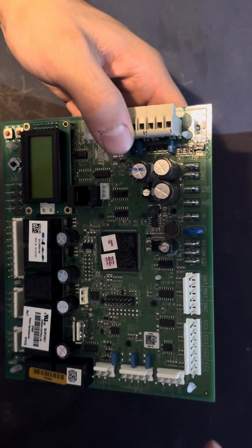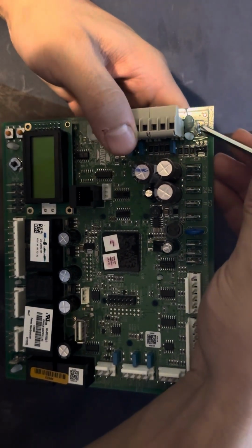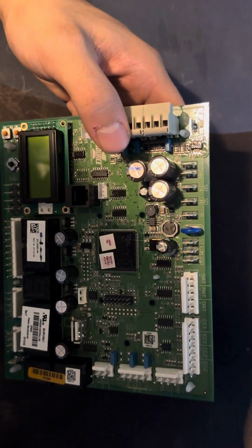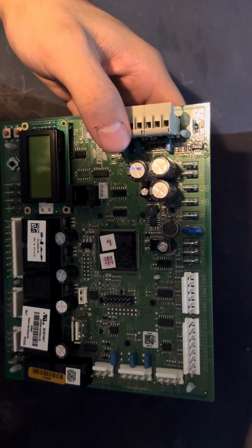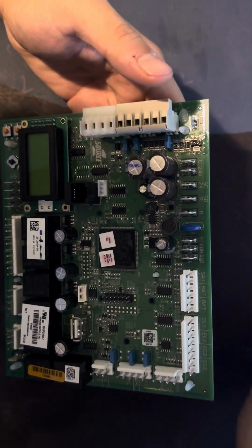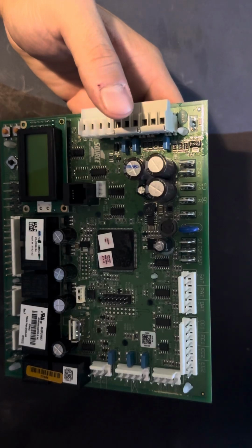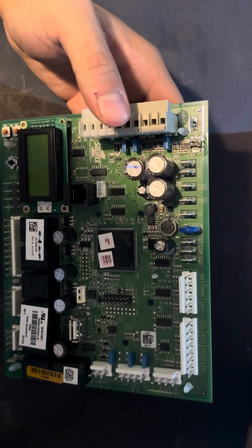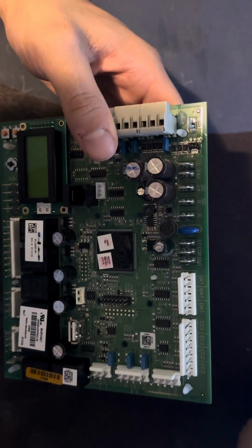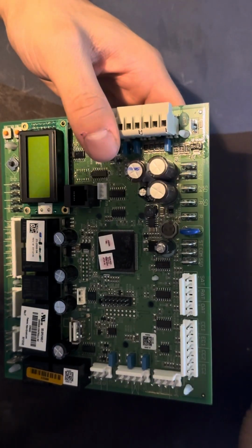Okay, so I should always be seeing 24 volts on this limit terminal over here. Actually, now that I say 24 volts, we're probably going to be looking more towards 26, 27 volts. 24 is maybe a little bit on the threshold, and then you're going into the lower side of the voltage, where you're actually causing a low voltage drop.